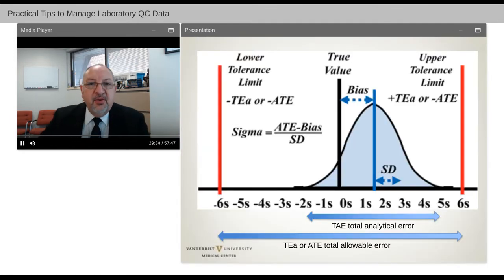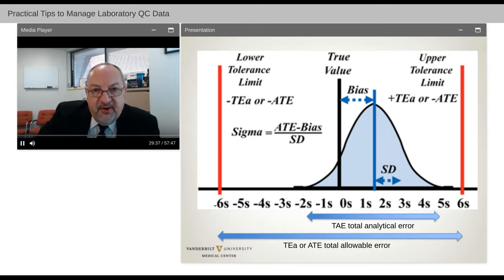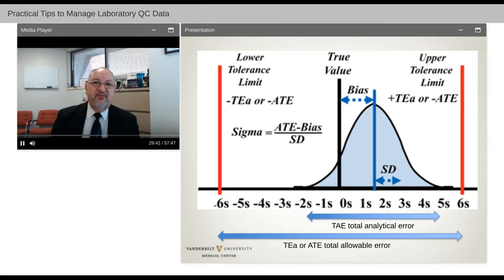We want our total allowable error in the red bars to be much wider than the analytical performance of our analyzer in this bell-shaped blue curve. Otherwise, we aren't meeting clinical performance. So having a much wider biologic variation, or total allowable error, allows our analytical performance to shift slightly from one day to the next, or one calibration to the next calibration, without going outside of our allowable limits.